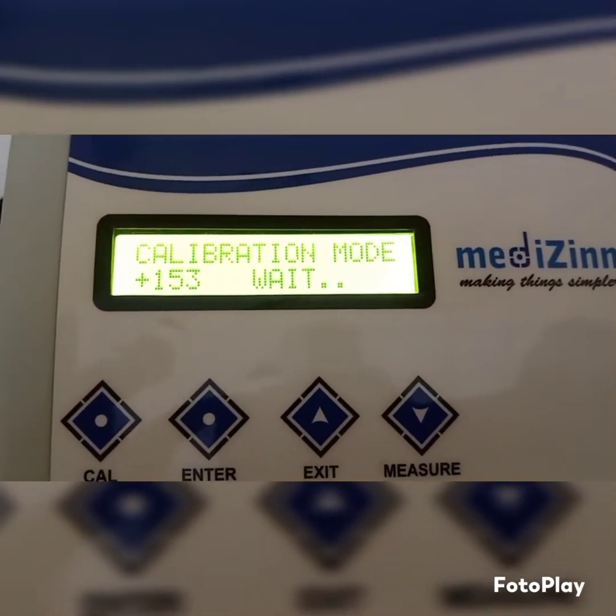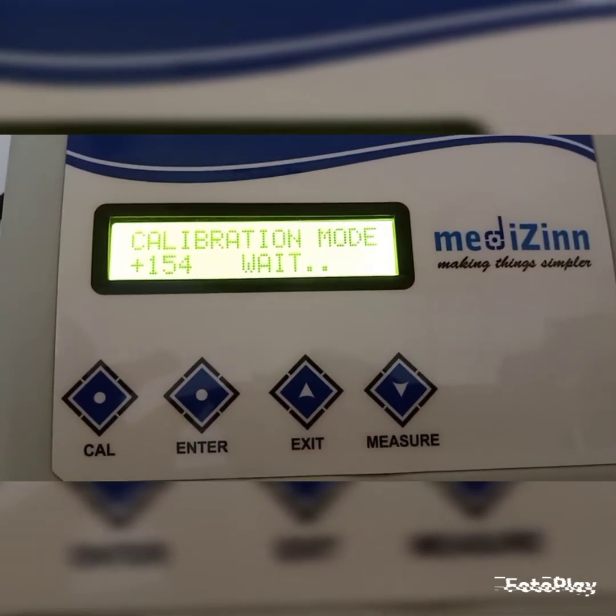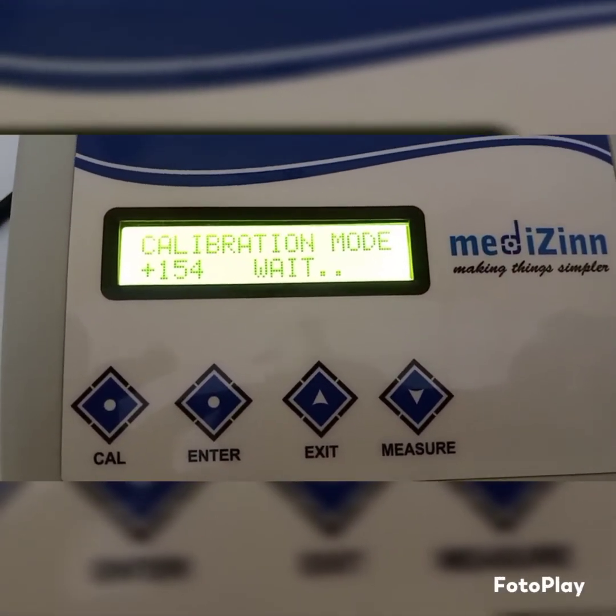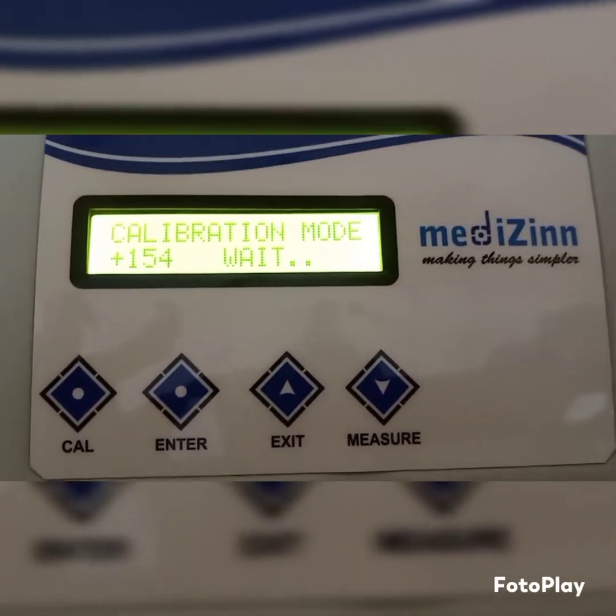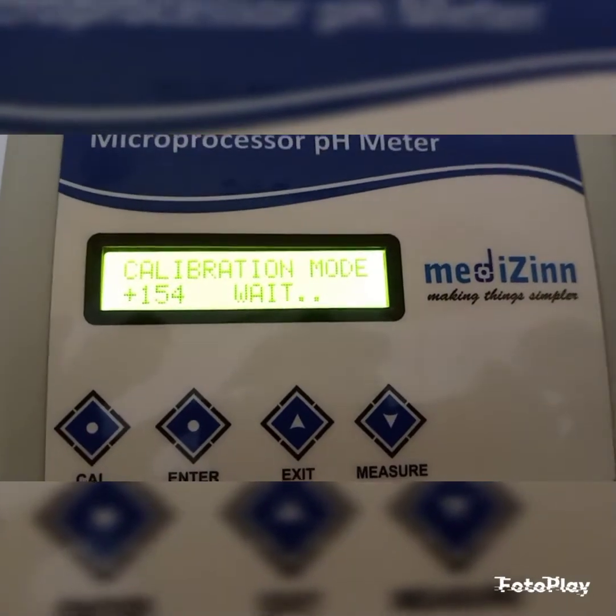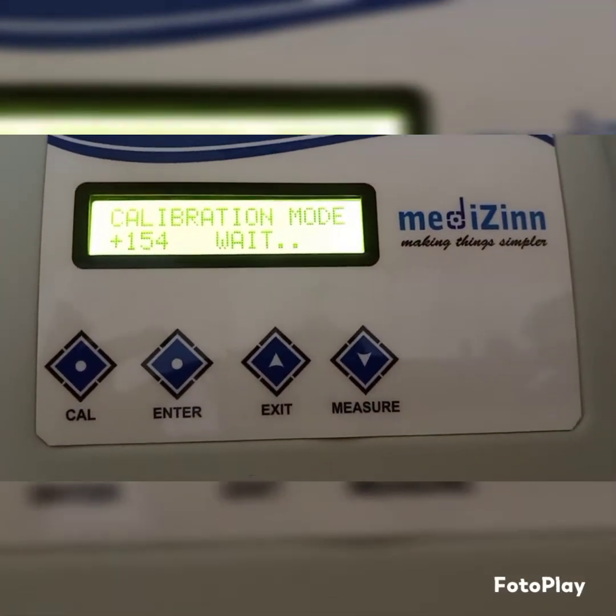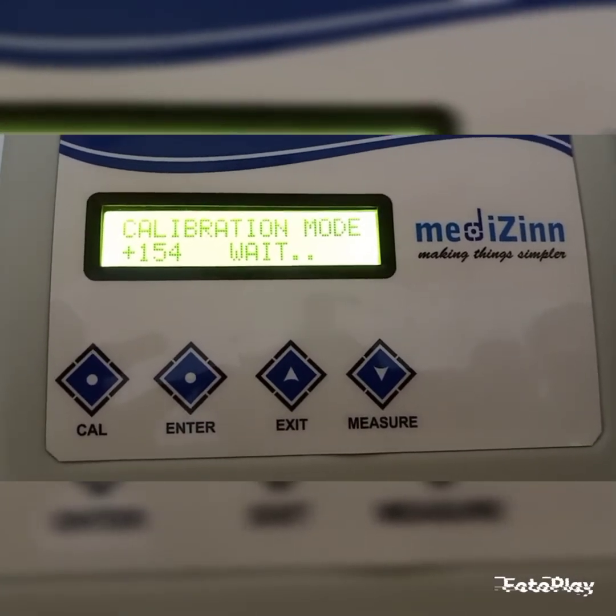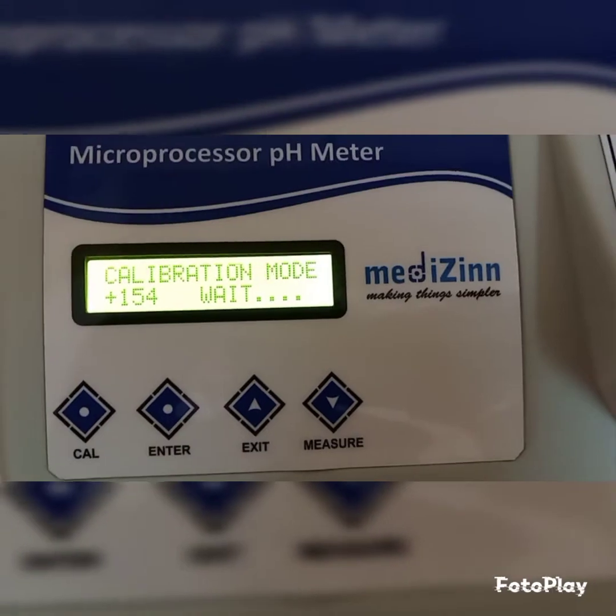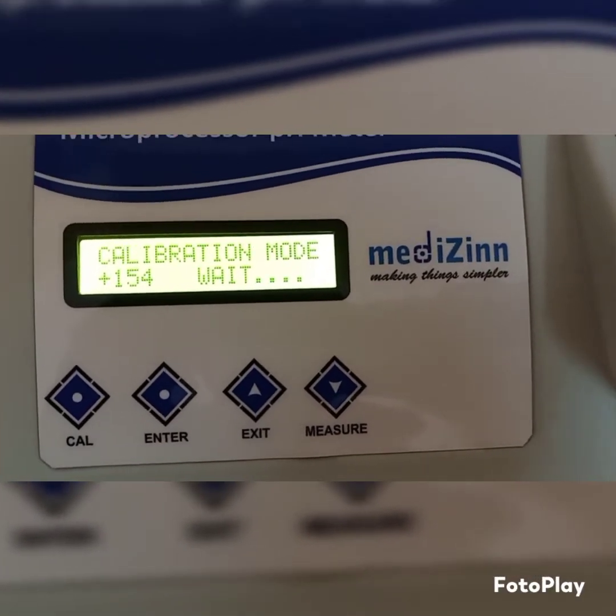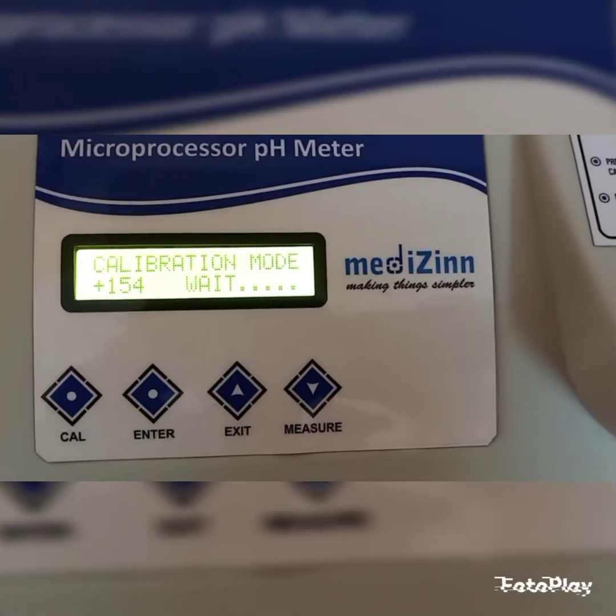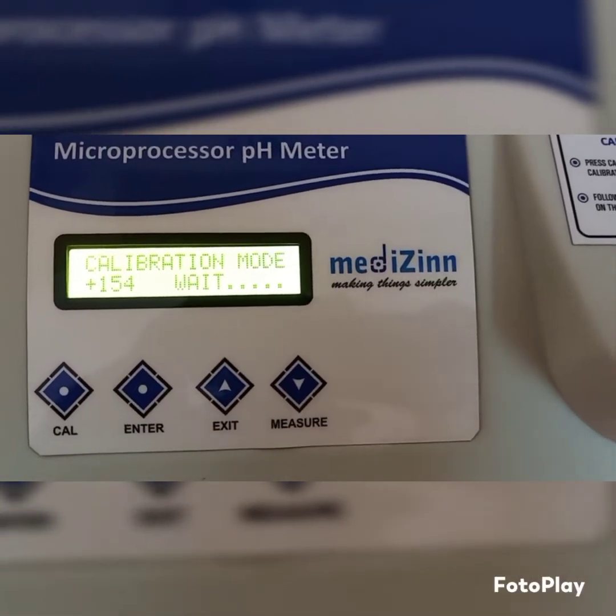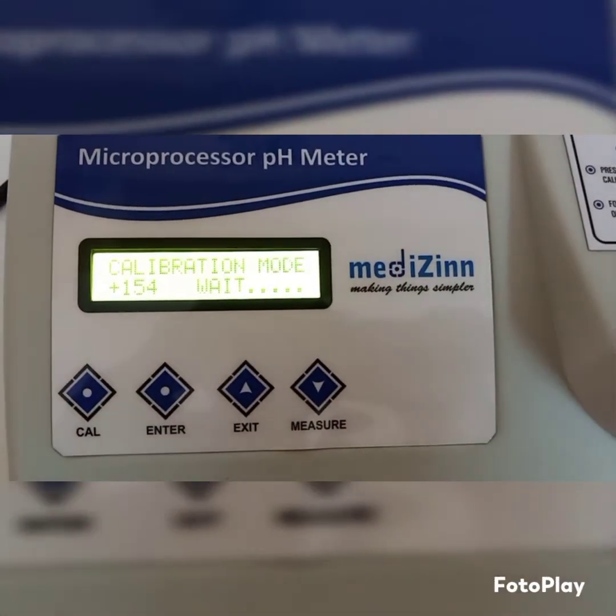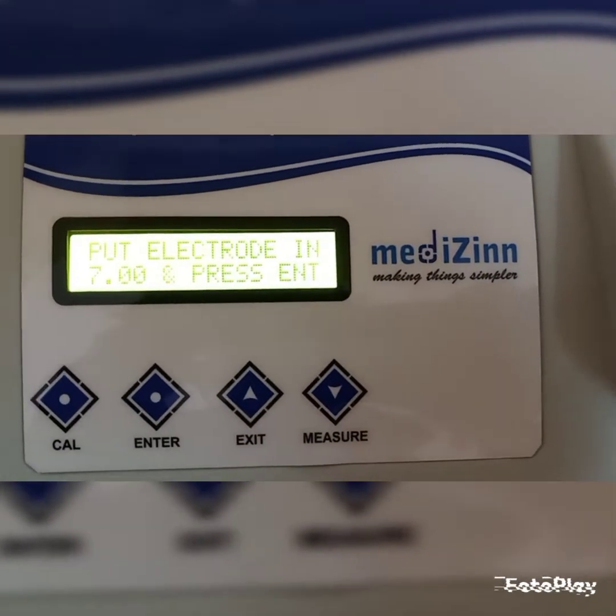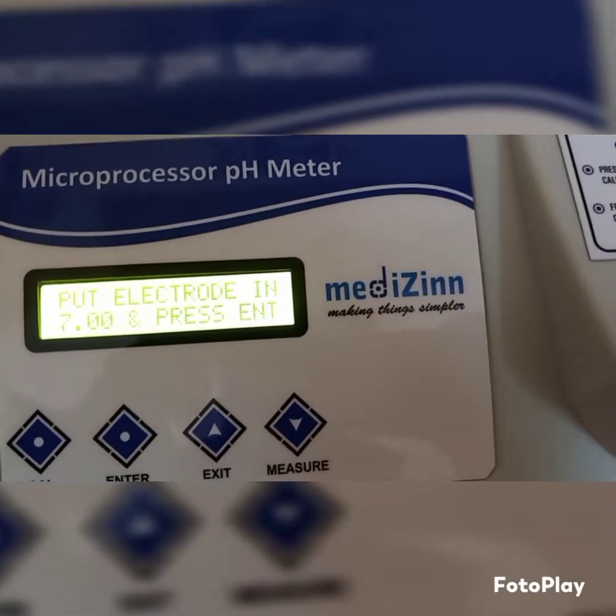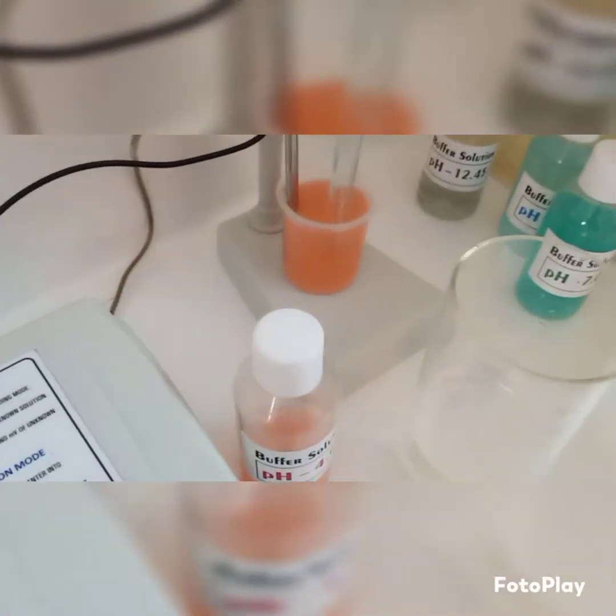Again that should be stable. That value may be 160, 170, 140. That's just an analog value. You just have to care that this should be stable. So again we have to wait for approximate 2 minutes for the calibration process of 4 pH over. 4 pH completed. Now again do the same process.